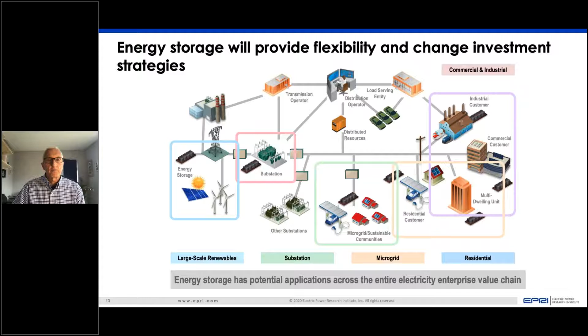But it does raise a whole new range of power quality concerns, compatibility concerns. There's a lot of exciting investigation here, and one of those is what happens at these higher frequencies, the switching frequencies of the inverters and rectifiers used for electric vehicle chargers, energy storage devices, or photovoltaic generation. This chart shows signals in a range of about 4 to 50 kilohertz, just as an example. Those are frequencies that don't behave like the 5th harmonic or the 7th harmonic. The resonances can be very localized for those higher frequency conditions.